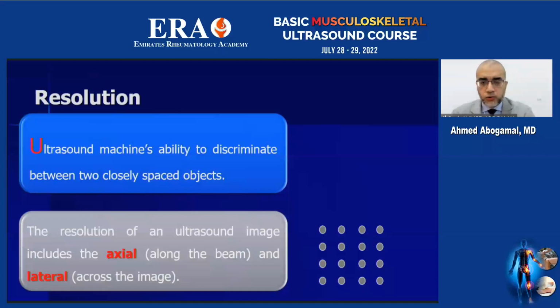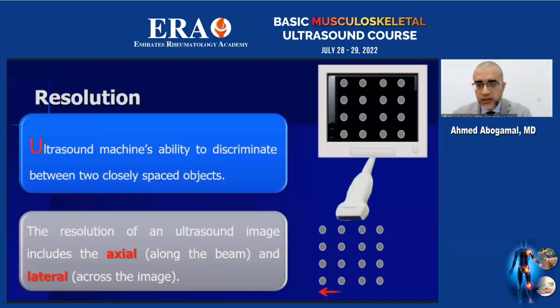The fourth point is the resolution, which is an important parameter to have good image quality from the ultrasound machine. It is defined as the ultrasound's ability to discriminate between two closely spaced objects, or dots, as you are seeing here. As we have different dots here, if the ultrasound machine can define these two dots and display them as separate dots on the ultrasound screen, that means this ultrasound machine has a good resolution.